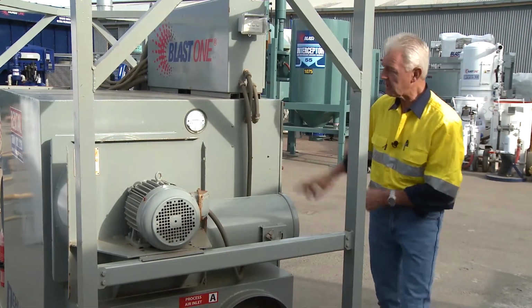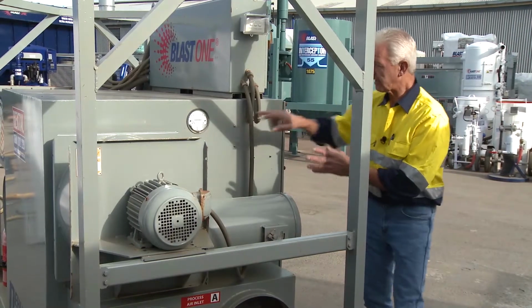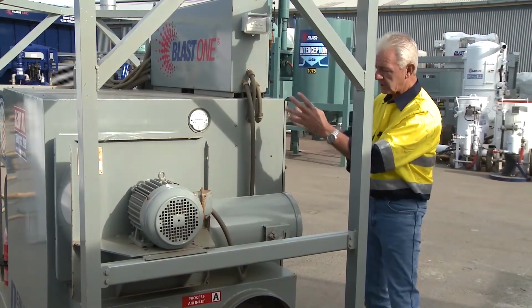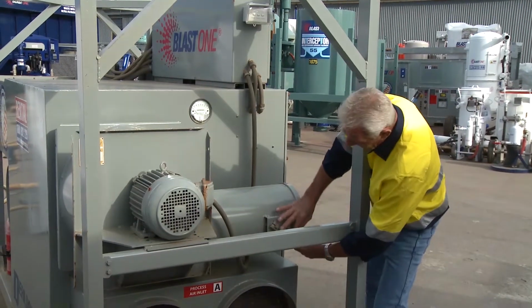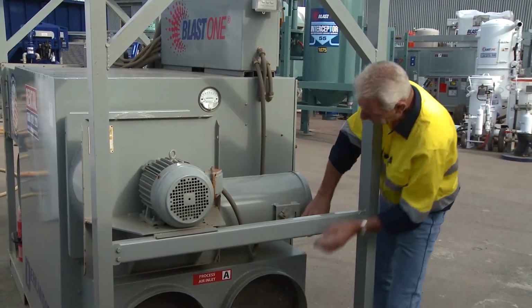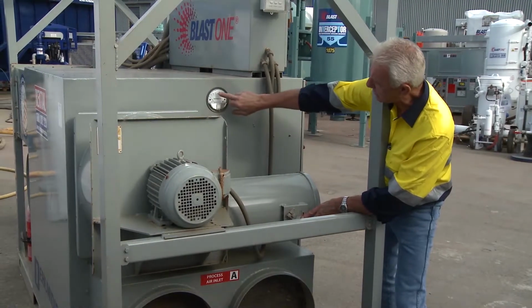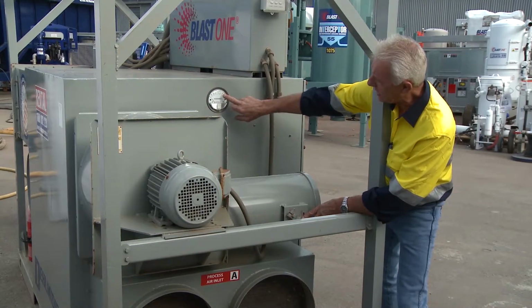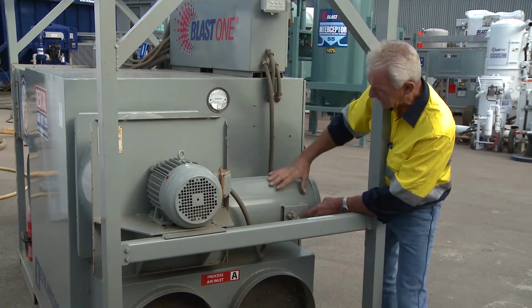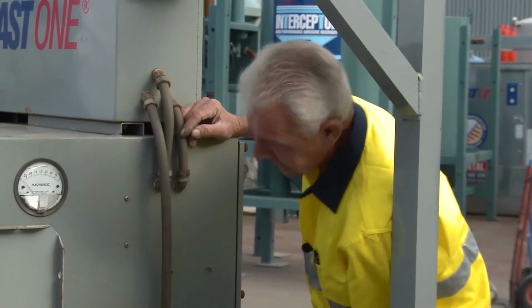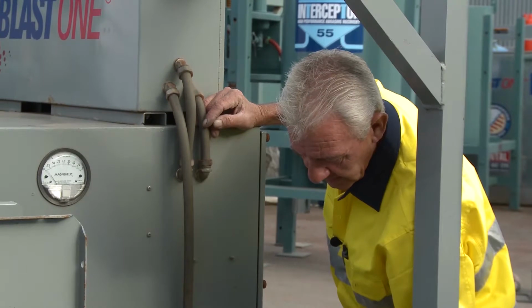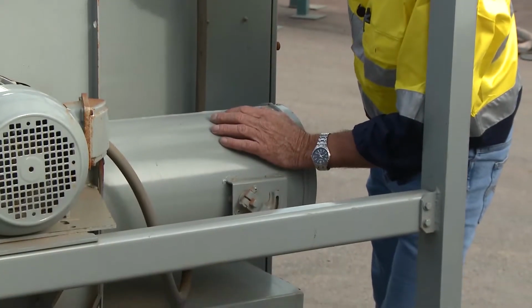I don't need that, but this gauge here gives me the opportunity to start to equal things up. This particular butterfly valve is what I'm adjusting to get this particular end up between 1 and 1.25. That's where I need to try and keep this end. So this gauge here is indicative of this butterfly here. This butterfly valve governs this gauge, and where I want this one is 1 to 1.25.